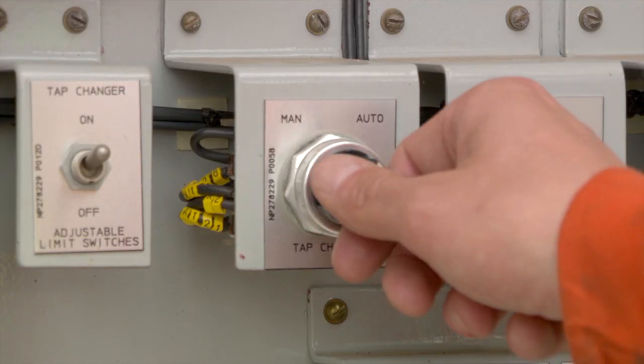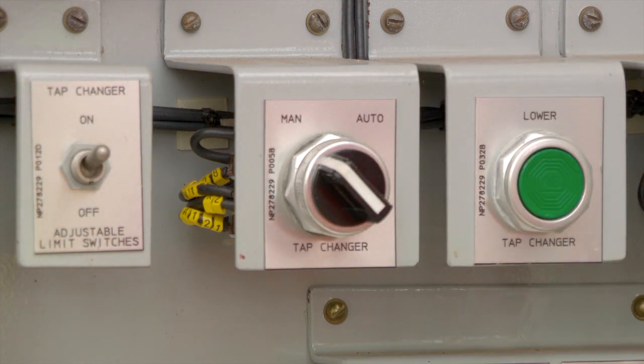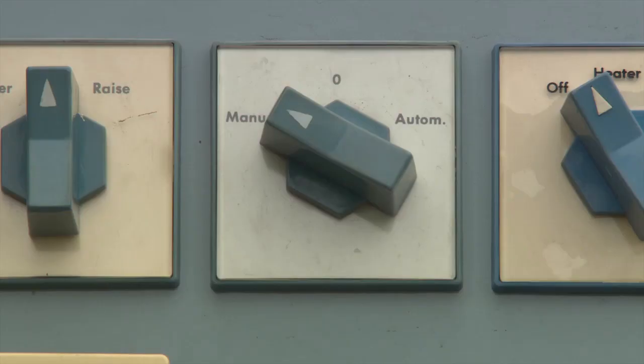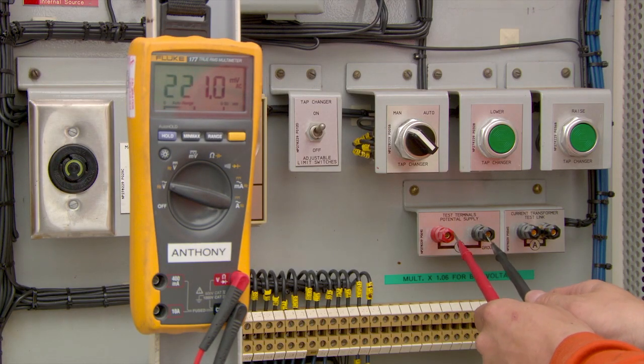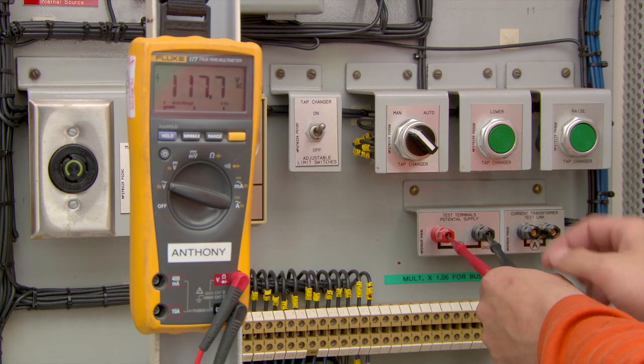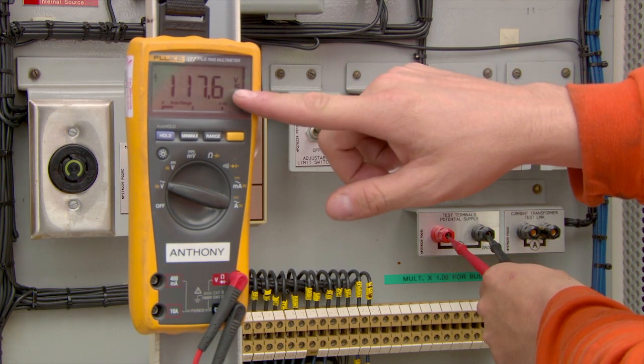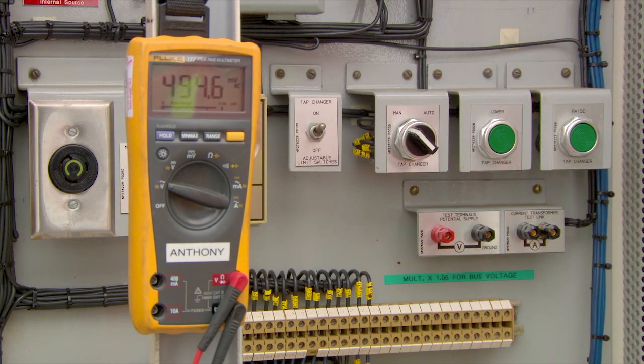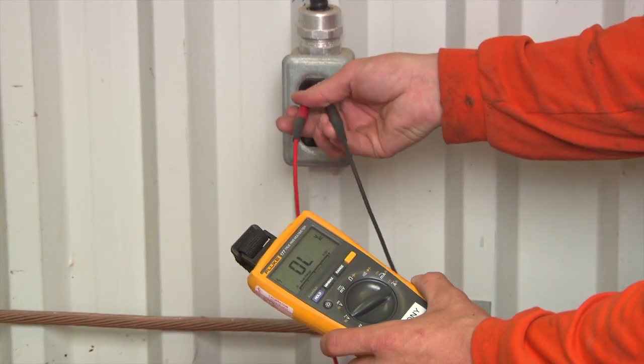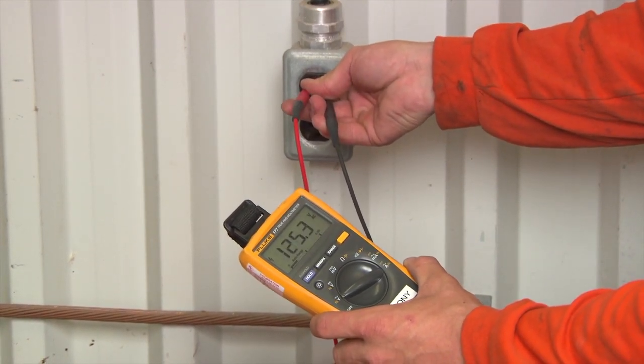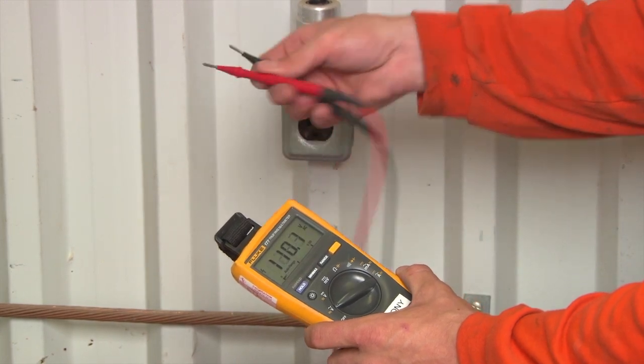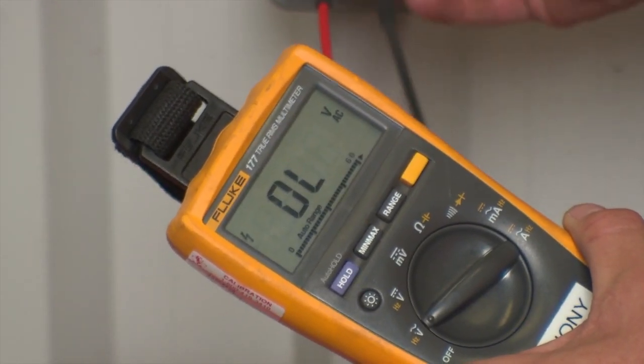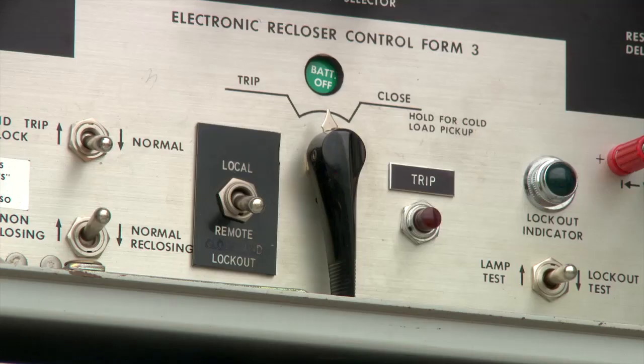Place the station ULTC control switch in the manual position. This switch is located in the station's transformer mech box. Check that the MUS ULTC is in the manual position. Measure the secondary voltage of the station. If required, adjust the MUS secondary voltage using the ULTC to maintain proper parallel voltage between DS and MUS. The MUS should be approximately 3 to 5% higher than the DS. Metering units and bus PTs may have a non-standard ratio. This will require calculation. Close the MUS F1 recloser.